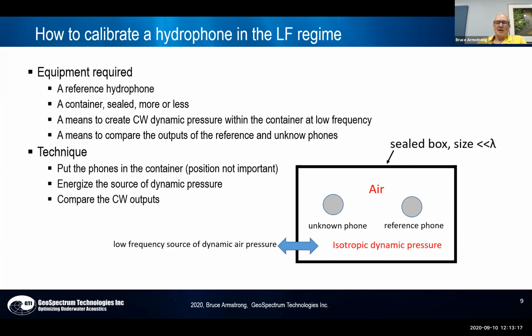And here is the essence of how you do it. I'll show you some real life examples. But what you need is a reference hydrophone. You need a container that's sealed, more or less. It doesn't have to be perfectly sealed. You need a means to create a continuous wave dynamic pressure within the container at a low frequency. And you need a means to compare the outputs of the reference and unknown phones.